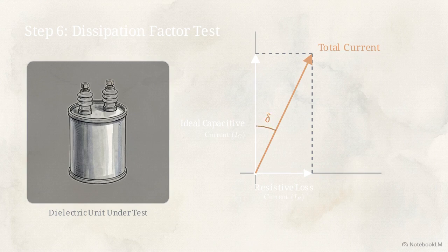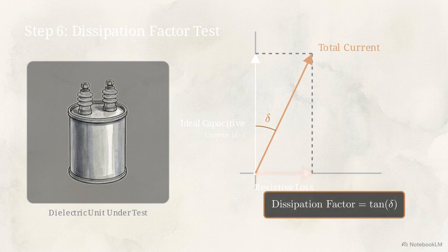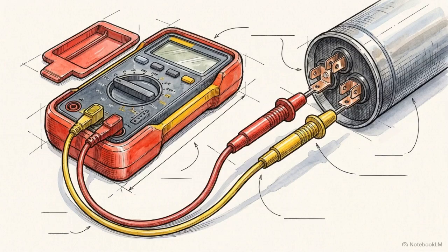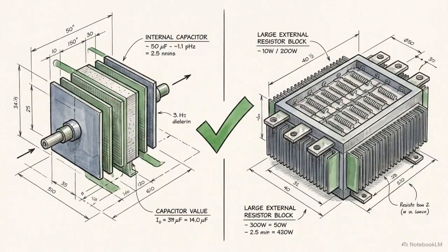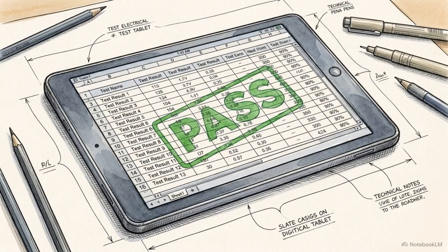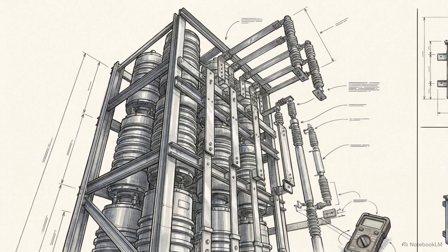As shown in the phasor diagram, the angle delta represents the energy lost as heat within the insulation. Step 7 involves measuring internal resistance and capacitance for every unit. This allows engineers to cross-reference with the external resistors and detect any capacitance mismatch that could cause an unbalance. These discrete dead-state tests mathematically map the health of the bank. By completing the first 8 steps, the team ensures the asset is physically ready for voltage.